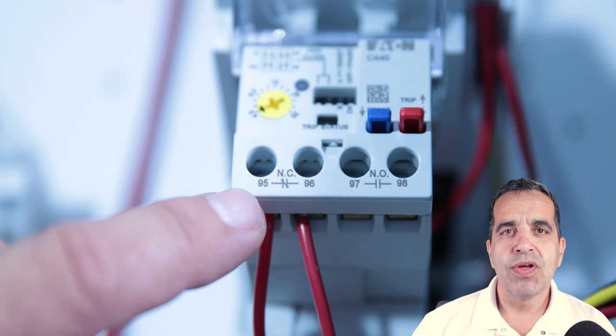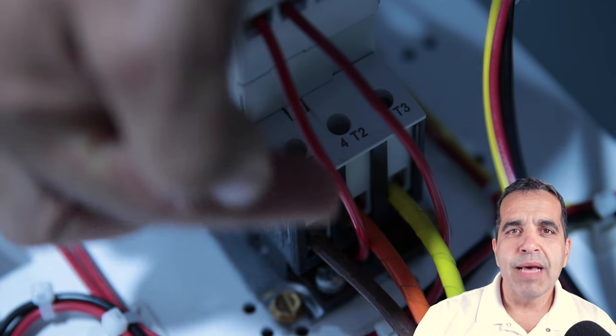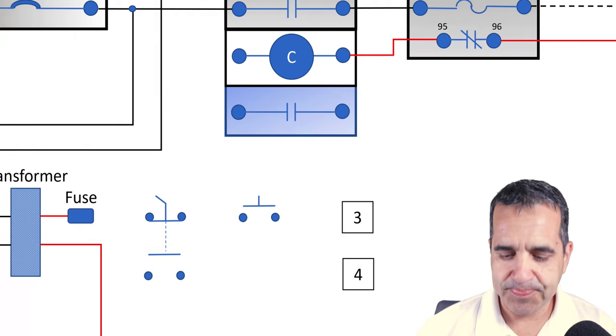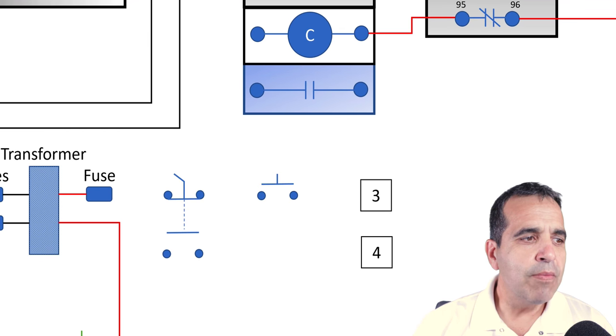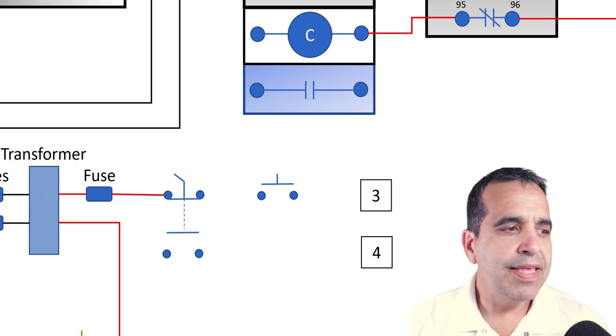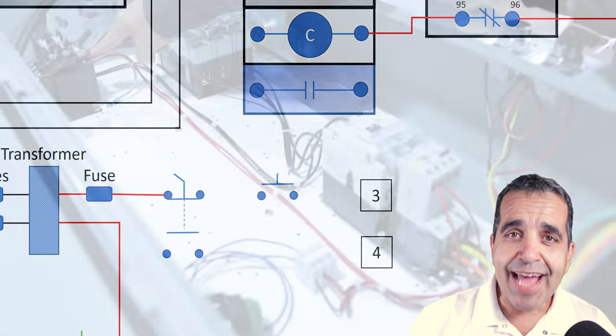From terminal 95 on the overload, the wire is going underneath the starter and coming up and feeding one side of our motor starter coil. Then from our fuse, we're feeding our selector switch, our hand-off-auto selector switch.